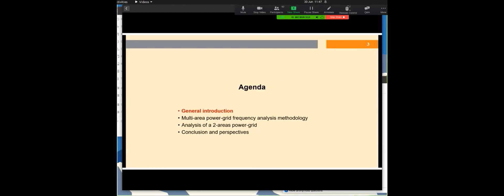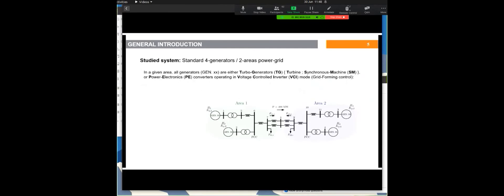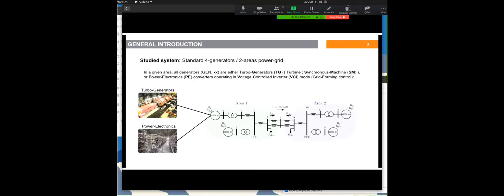The context is the massive integration of renewable energy on power grids using power electronics converters. These converters are controlled in grid-forming control mode, so they give assistance on frequency stability. The objective is a methodology to perform frequency stability analysis on a large power grid with several frequency areas, and to verify the impact of replacing turbo generators by power electronics on the quality of frequency analysis results. The studied system is the well-known standard four-generator two-area system, where each generator is either a turbo generator using synchronous machines and turbines, or a power electronics converter operating in voltage-controlled inverter (VCI) mode, also called grid-forming control mode.